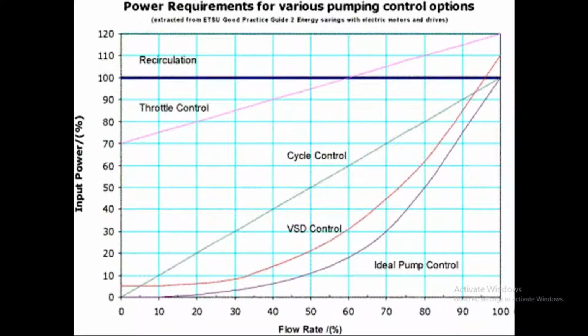Now the inverter type VFD has also come for the fridge compressor. Instead of switching on and off on the thermostat, this inverter reduces the kilowatt or watt consumption in our domestic fridges. Likewise, the VFD control, the variable speed drive, consumes only 10% at the start of flow rate. Even at 50% of the flow rate, this consumes only 20% of the input power. At 80% of the flow rate, this consumes only 50%. This is the main purpose of putting the VFD on the blower.